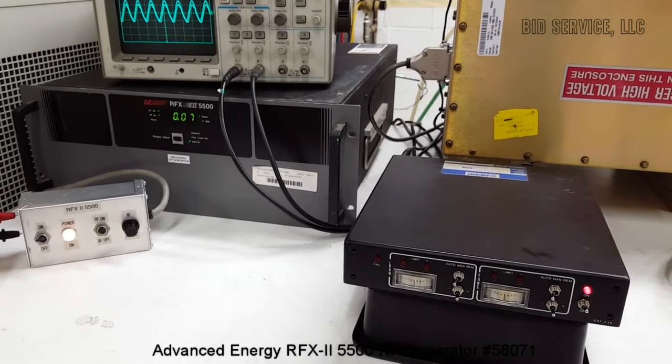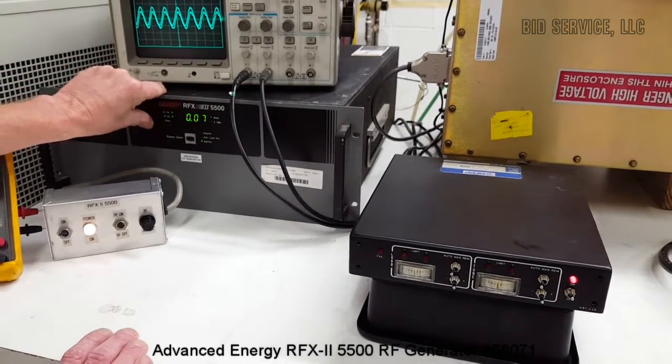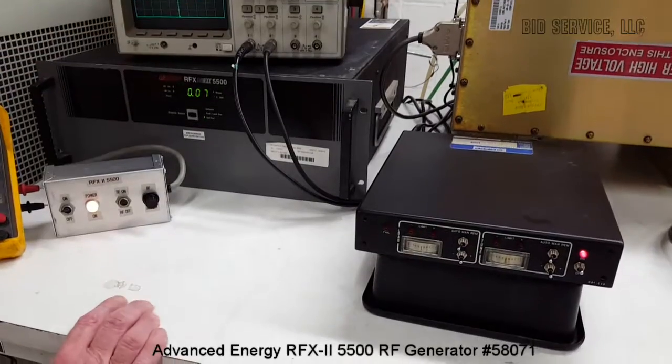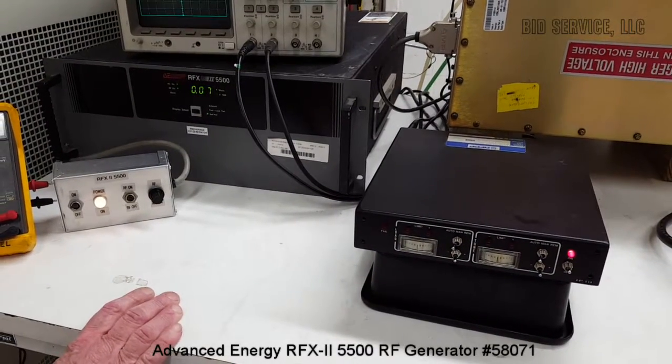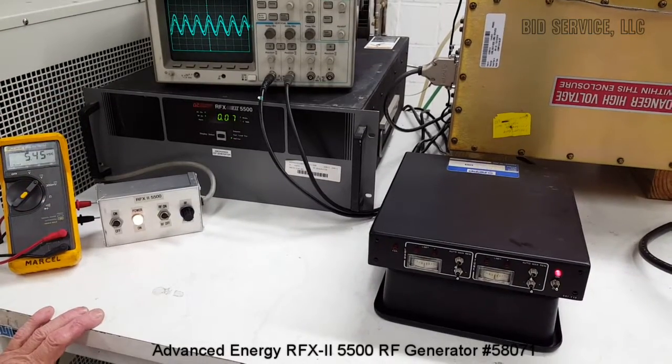What we try to achieve is the lowest reflected power level as possible. Normally, our threshold is about 5% at 1,000, so this is more than acceptable for 3,000.